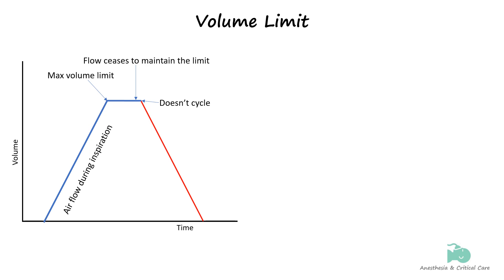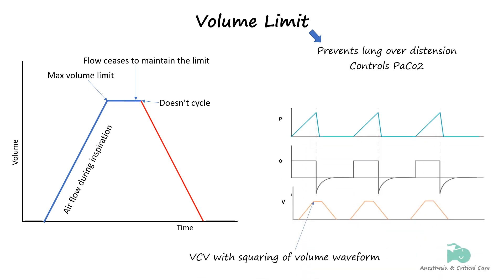The volume limit ensures that there is no overdistension and lung trauma, and helps maintain tight control over minute ventilation and partial pressure of carbon dioxide in arterial blood. Volume limits are employed in volume control ventilation where we find squaring of volume-time waveform.